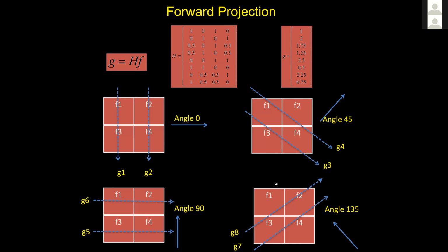In this type of algorithm, there are two key operators. We call them the forward projection and back projection. Basically, given an image, you have a system matrix that shows the mapping from each voxel to your detector measurement. We call this forward projection, basically from image space to the detector space. You can very nicely model this as a matrix times a vector. This is forward projection.